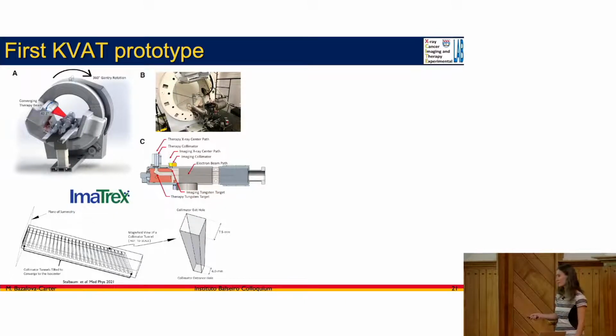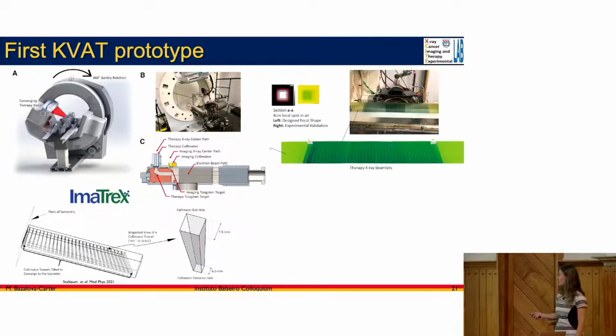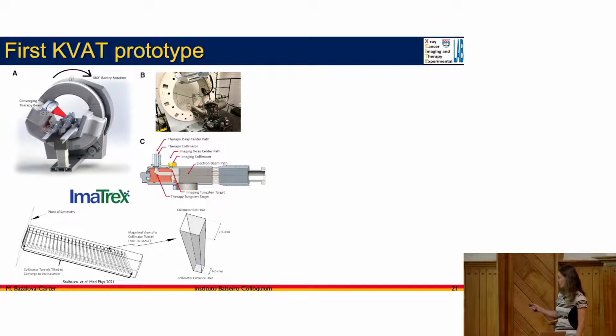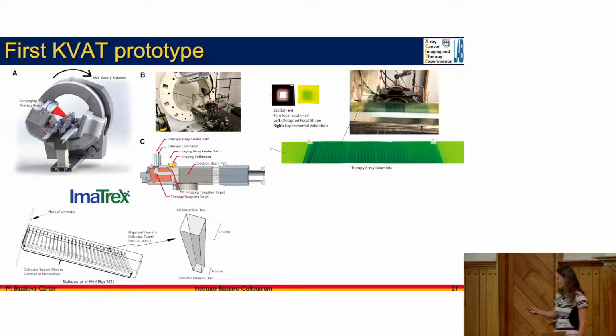They basically changed up the design a little bit, maybe just for manufacturing purposes, and instead of cylindrical holes or divergent cylinders, they now had rectangular holes, but the principle was exactly the same. And this is what happens. This is actually a nice photograph of the Gafchromic film that they used. And this is what happened when they put a number of films just in front of the collimators. And you can see all these little beamlets, diverging and converging at the same time.